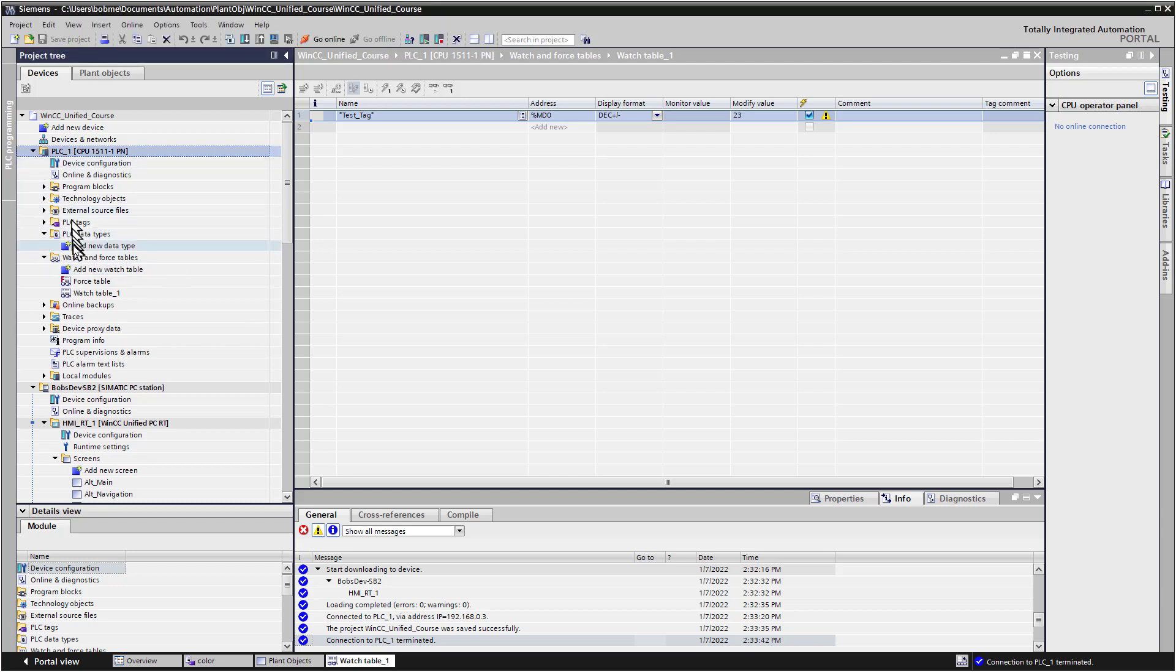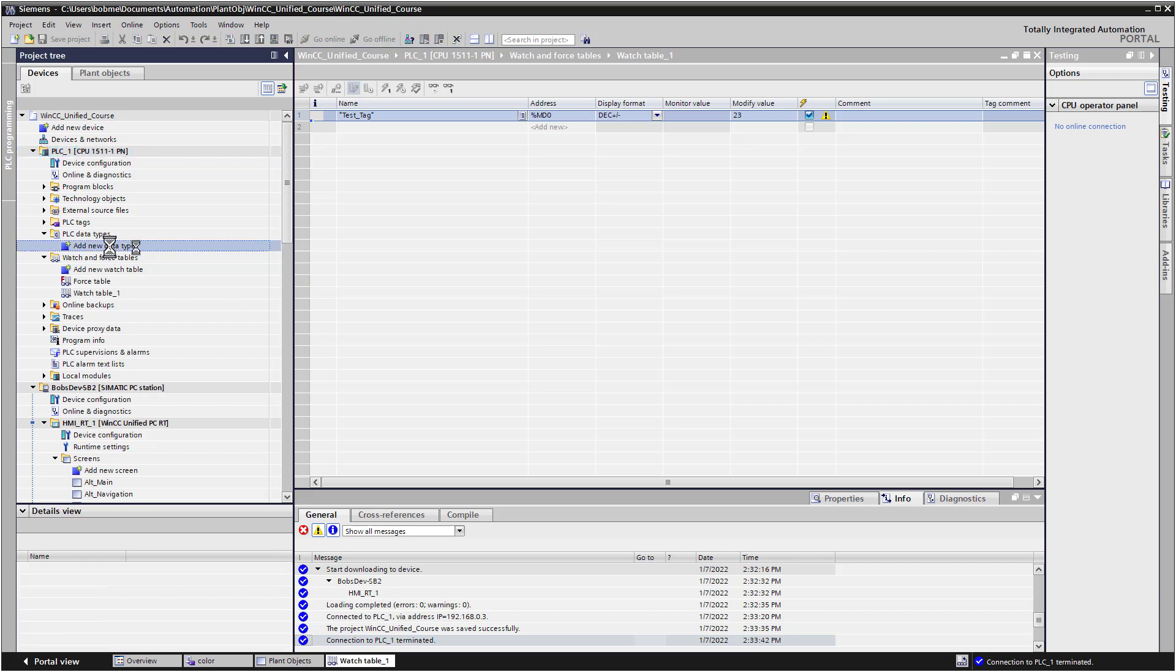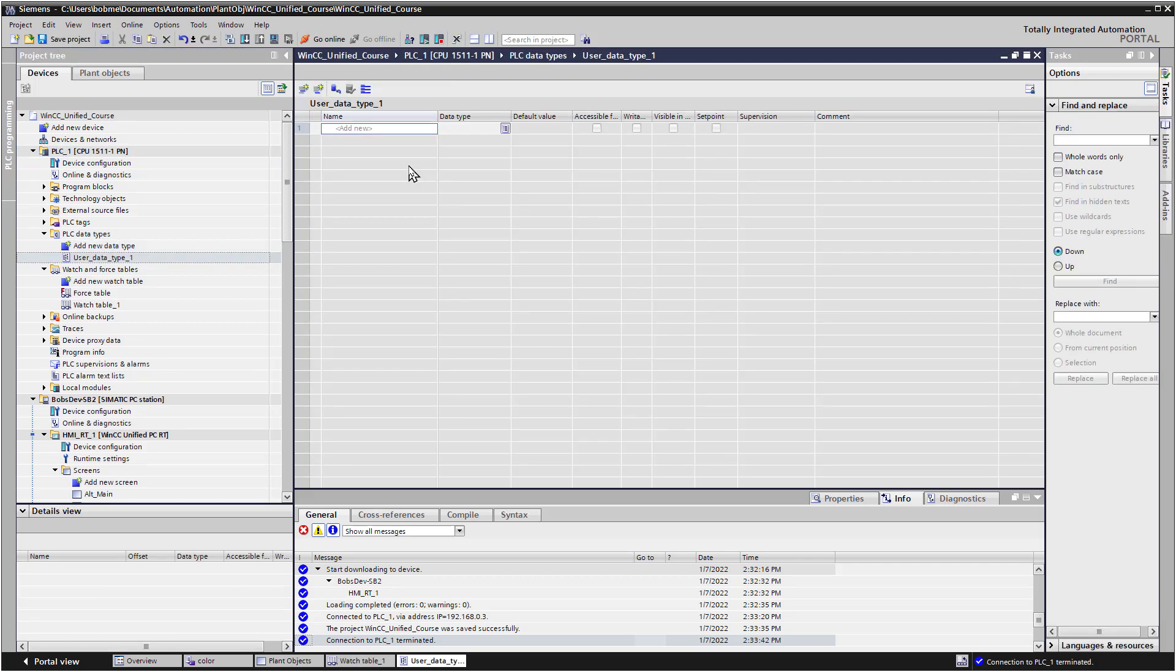So under my PLC, I'm going to go to PLC Data Types, and I'll just click Add New Data Type. So we're just going to create a generic UDT where each piece of equipment has a name, a state, which would be on or off, and a process value, which depending on the equipment, if it's a pump, it might be gallons per minute. If it's a motor, it might be RPM, stuff like that.